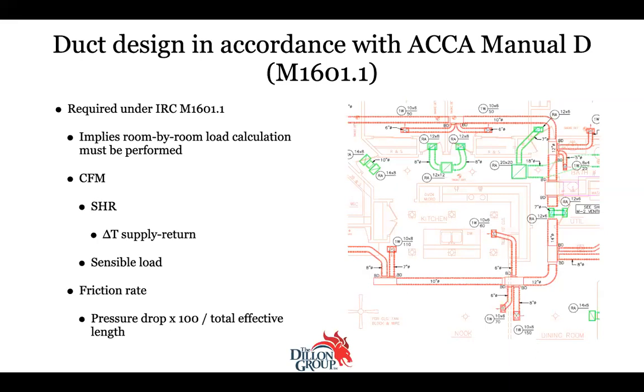It's not hard to do. A lot of the load calculation software has add-on modules where you can literally drop in the blueprint and sketch out the duct design, and it'll tell you, from the load calculation, here's how much air you need to deliver. And then you can work out what size, here's all the devices and all the structure of the duct system between this point and that point, how do we make that work? It tells you everything you need to do, and you can walk through that way. Again, it's not complicated, but if you haven't read Manual D, you're not going to know how to do that in the software.